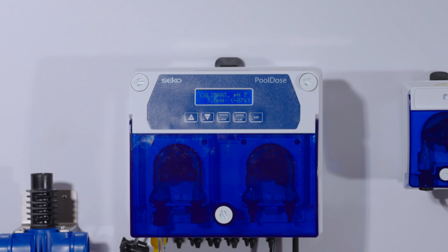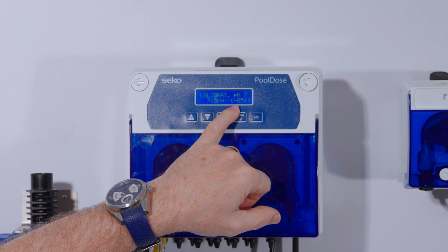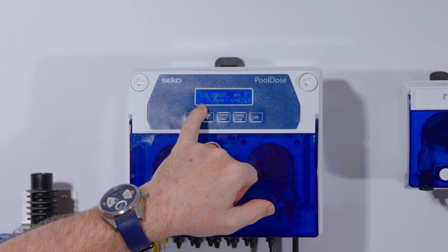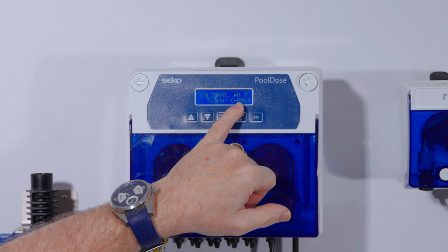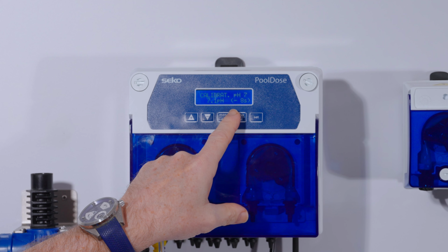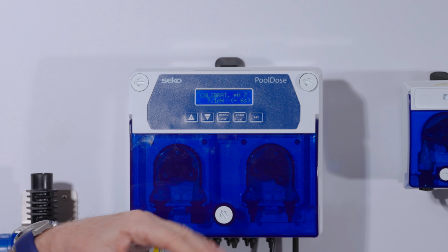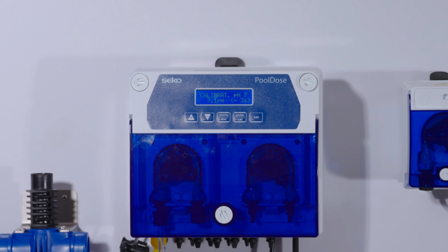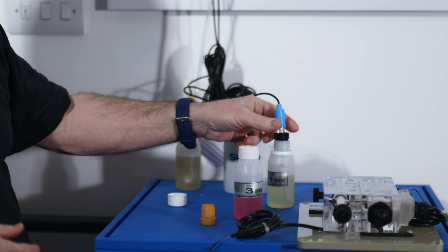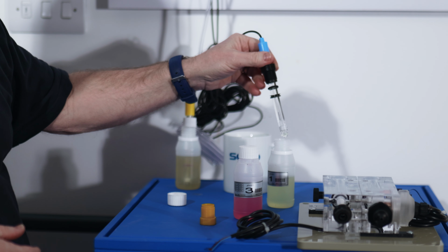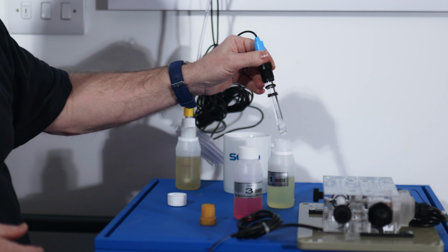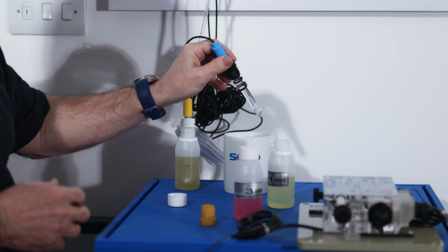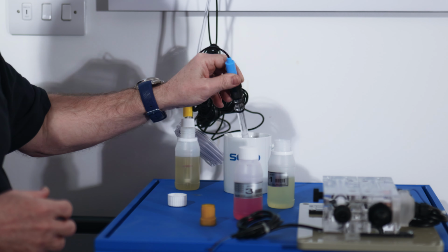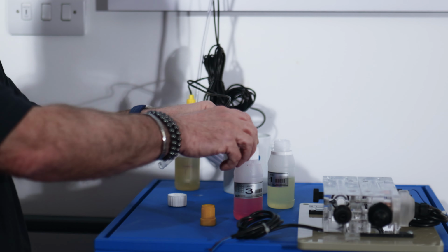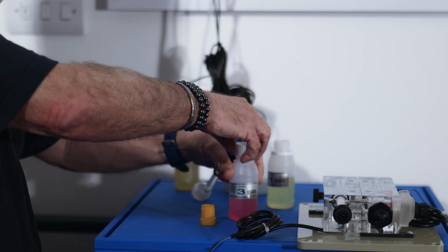The calibration now begins to count down from 90 seconds and we can see that it's specified the 7 pH solution on the calibration. As the countdown continues, when it reaches 0 it will give you a percentage of the probe's accuracy. Here we can see that it's come back 100% quality. We can then take the probe out of that buffer solution, giving it a gentle shake, and we can either wash it in some clean water or just give it a little general shake just to get some of the residue off. We now open the 4 pH buffer solution and place the probe in that.